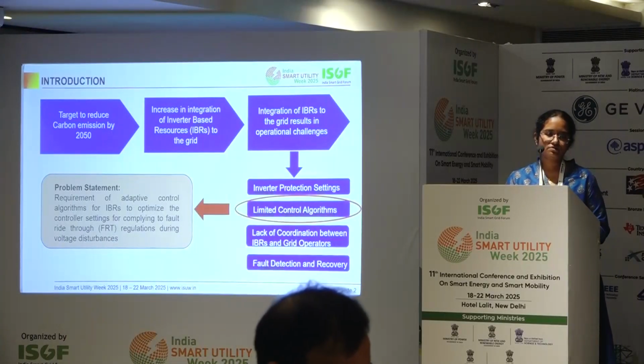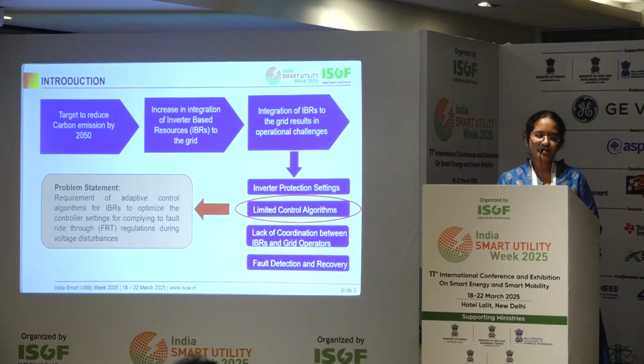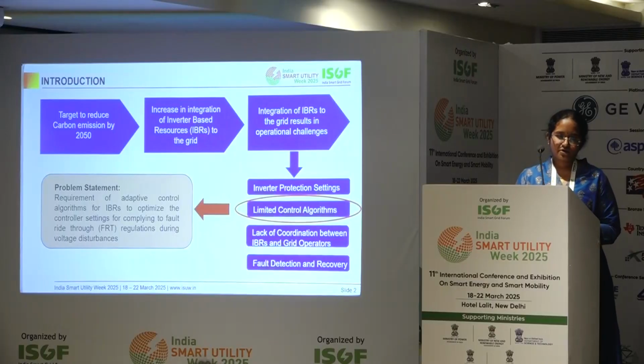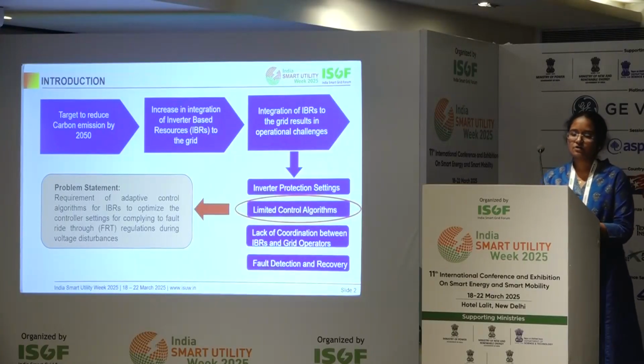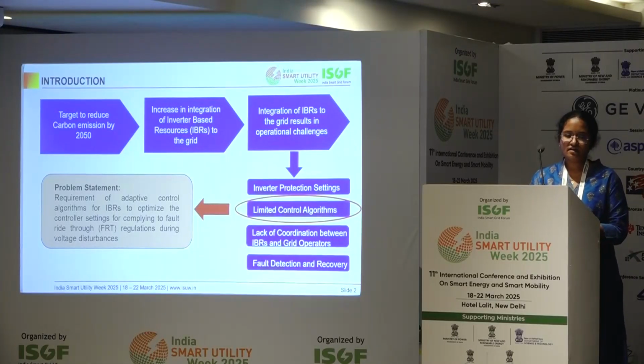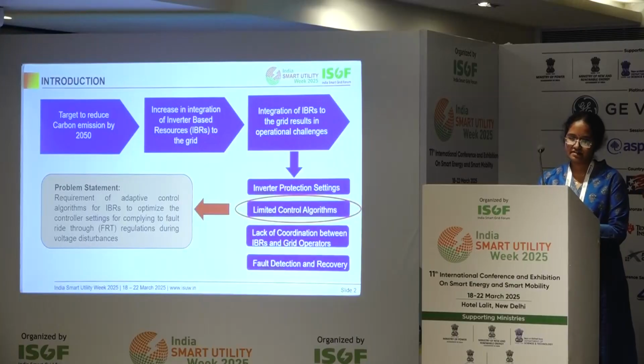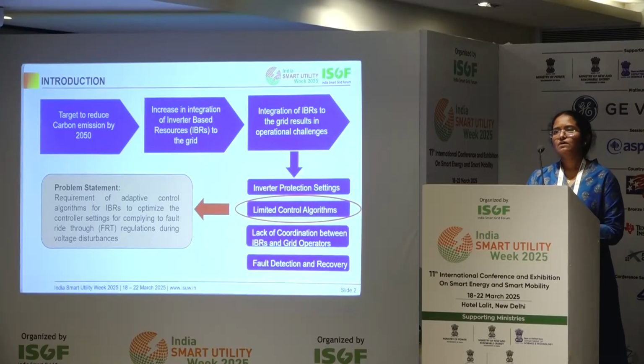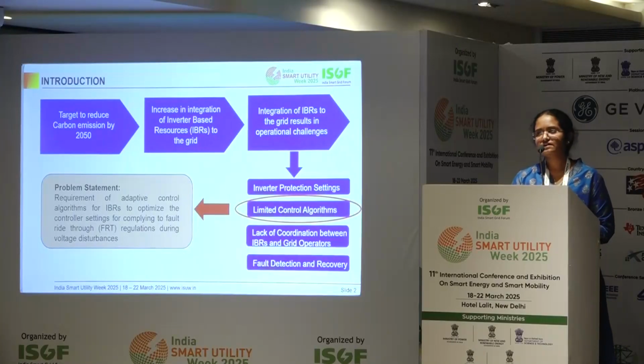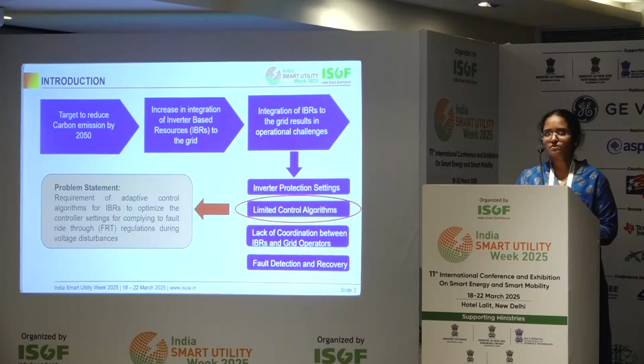I have listed four major operational challenges: inverter protection settings, limited control algorithms, lack of coordination between IBR and grid operators, and fault detection and recovery. In this case study, we have concentrated on limited control algorithms. We propose that voltage and frequency fluctuations should not depend only on the LVRT control algorithm settings, but that the control algorithm should also consider the topology of the grid into which the IBR is connected.